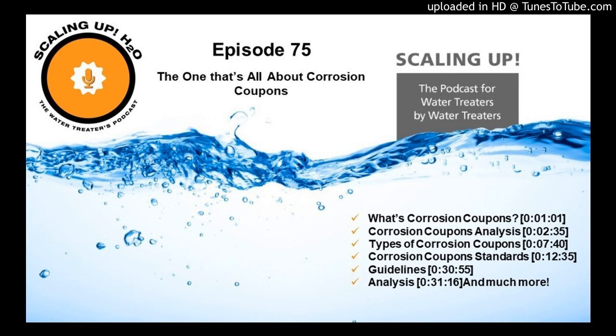Quite simply, corrosion coupons are little pieces of metal, and they can be any metal. I had a question come up: are the only types of metals you can get in corrosion coupons mild steel and copper? No, there are literally thousands of alloys you can get corrosion coupons made from. If they build a piece of equipment out of a certain type of metal, I promise you can find that same alloy in a corrosion coupon. So quite simply, corrosion coupons are these little slips of metal that we put into a system, and they mimic the same type of metal that the system has.